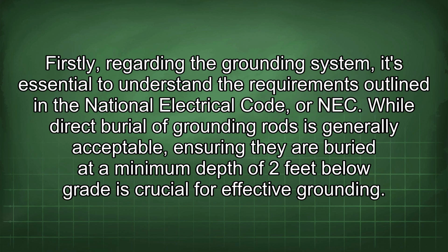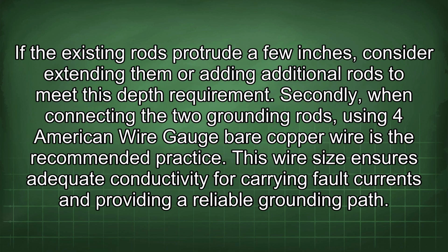Firstly, regarding the grounding system, it's essential to understand the requirements outlined in the National Electrical Code, or NEC. While direct burial of grounding rods is generally acceptable, ensuring they are buried at a minimum depth of 2 feet below grade is crucial for effective grounding. If the existing rods protrude a few inches, consider extending them or adding additional rods to meet this depth requirement.